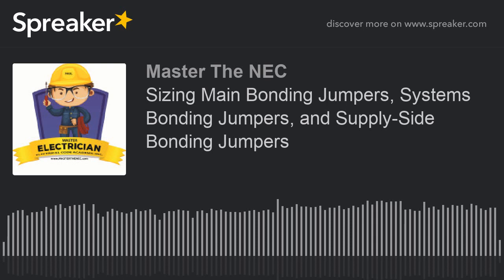So, on today's podcast, we're going to dive into grounding and bonding a little bit. We're going to talk about main bonding jumpers and system bonding jumpers just a little bit, but probably spend most of the time talking about main bonding jumpers because we kind of take those for granted, and they have such a vital role in making sure that we have safe electrical systems. Sometimes we spend a lot of time looking at equipment grounding conductors, and they're extremely important, and in order to allow fault current to get back and clear an overcurrent device, we get it. And we look at all kinds of things at the neutral and all this kind of stuff, but we don't spend a lot of time looking at main bonding jumpers and the concept of a main bonding jumper, and we kind of take it for granted.